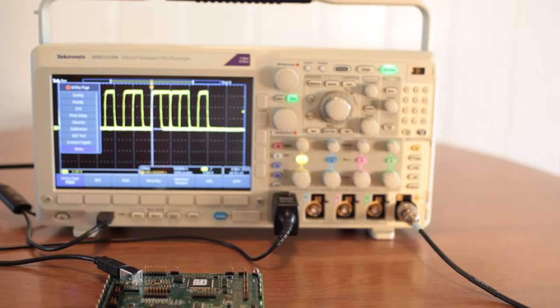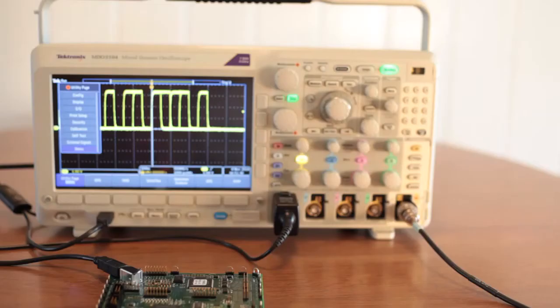These waveforms are obtained by connecting the ground reference lead to the ground terminal on the demo board and the probe tip to specified high terminals. It is suggested that the hook-type probe tip is used. Probe tips can be changed using available hardware. Prior to any demonstration, push Recall Demo Setup in the menu bar to the right of the display to automatically configure the oscilloscope for each demonstration.